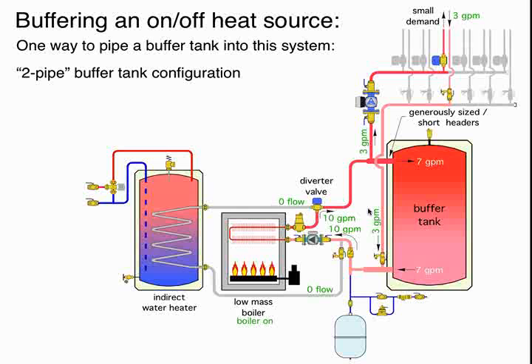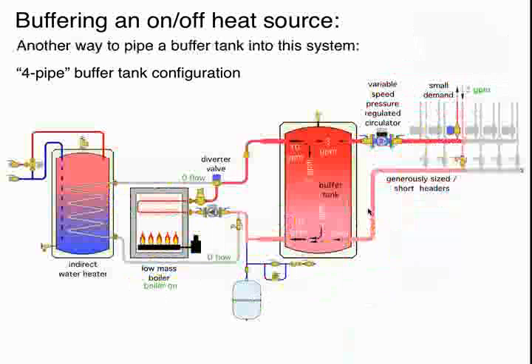Probably not, because actually when you look at this, it is mandatory priority in the sense that that valve's either going to go indirect or space heating. It can't do both at the same time. So I would stick with this arrangement. And again, I'd look at it from the standpoint that even when the boiler is supplying the indirect water heater, assuming that there's heat in the buffer tank, the space heating load can still remain active, which is the nice thing. It's priority, but at the same time we have energy flowing to space heating at the same time as we have energy flowing to domestic water because we have the buffer tank piped in like this.